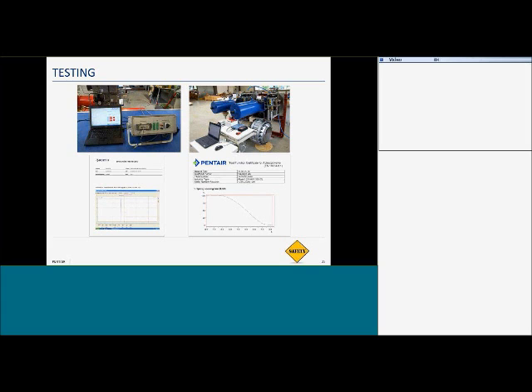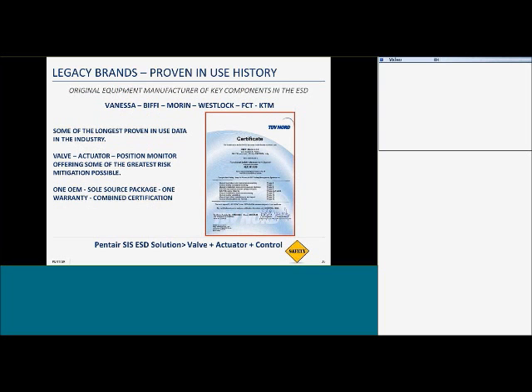But some of the testing criteria for these SIS packages is pretty extraordinary. This is an example of a package that we built for a customer in Germany. These valves, I think they were 12-inch Vanessa valves. They needed to close in 300 milliseconds. This is not only a challenging task, but I would say testing and proving it out is even more challenging. But this is the kind of work that we're doing at Pentair and the kinds of things our customers are asking from us when it comes to SIS. So we do see much more complex testing requirements when it comes to these safety shutdown systems.